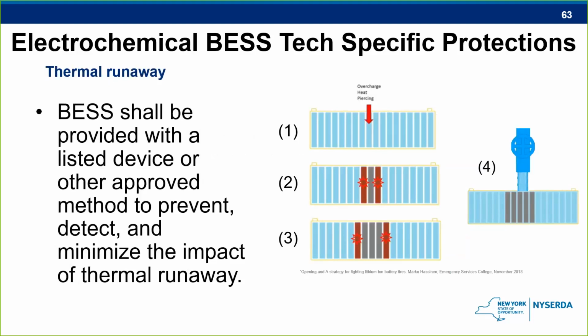And as I mentioned earlier, thermal runaway, once it's started, is very difficult, if not impossible, to stop within a cell. So energy storage systems should have a device that can recognize when the temperature is rising, and that device, the battery management system that we've talked about, should isolate that area and send a signal to the owner of the system that a problem exists. And testing has shown that stopping the charging and discharging of a cell is an effective measure to prevent the cell from even really going into full thermal runaway. And on the right side of the screen, it shows the stages of thermal runaway and how it can propagate to adjacent cells if it's left uncontrolled. So a method must be in place to prevent the cell from going into thermal runaway in the first place, and also to prevent the spread to adjacent cells.